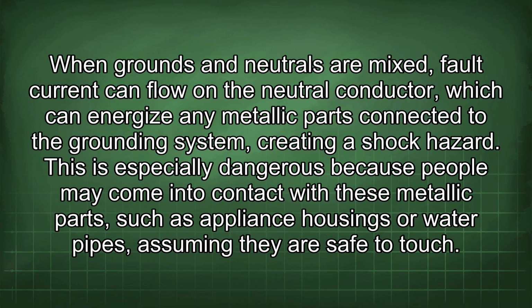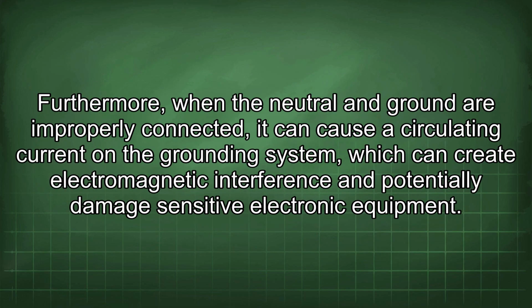When grounds and neutrals are mixed, fault current can flow on the neutral conductor, which can energize any metallic parts connected to the grounding system, creating a shock hazard. This is especially dangerous because people may come into contact with these metallic parts, such as appliance housings or water pipes, assuming they are safe to touch. Furthermore, when the neutral and ground are improperly connected, it can cause a circulating current in the grounding system, which can create electromagnetic interference and potentially damage sensitive electronic equipment.